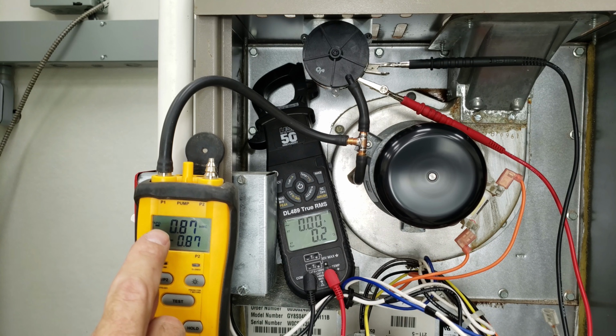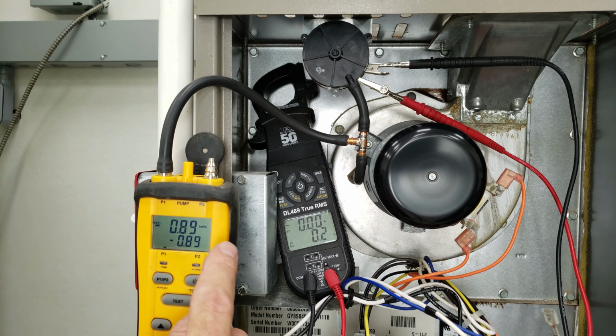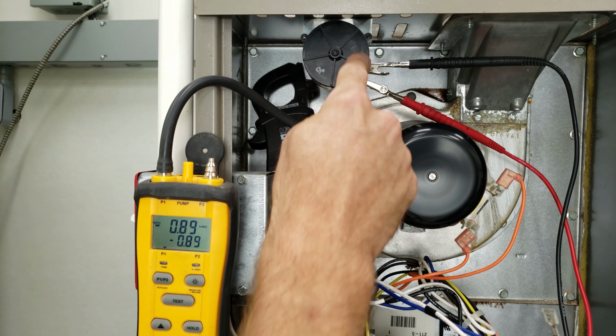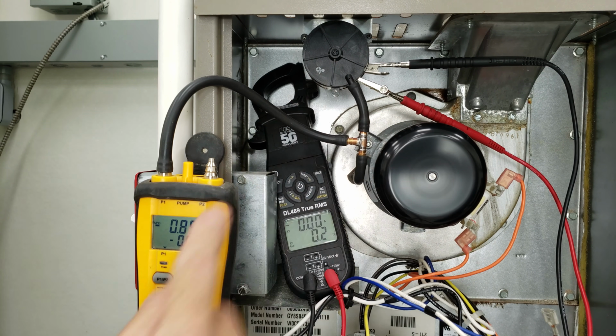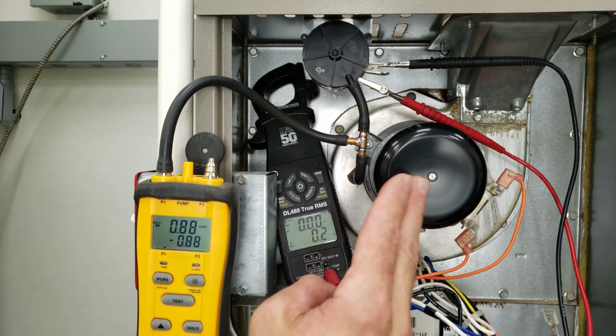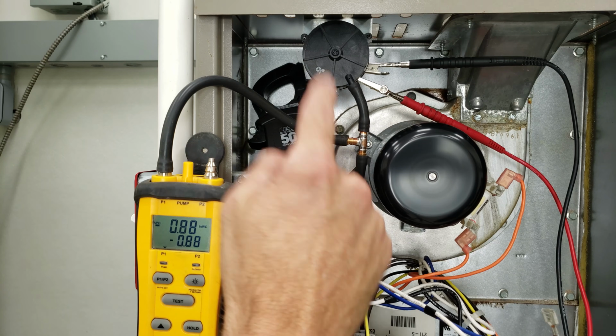We're measuring 0.87 inch water column. So we've reduced the pressure on this side, we've lowered it down that far, so say 0.9 or so. So everything is functioning properly, the inducer motor is running correctly, we unclogged the port, and everything's good.